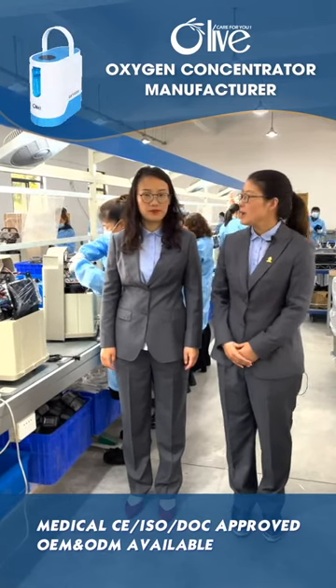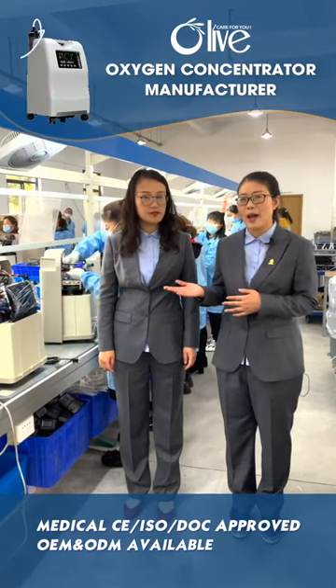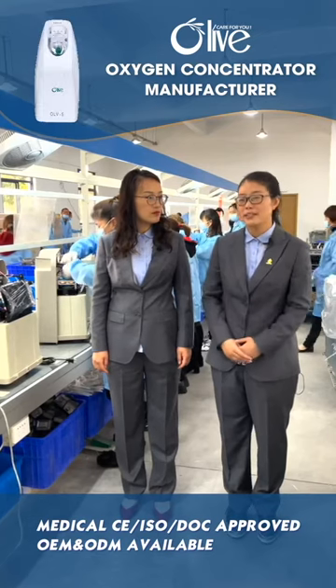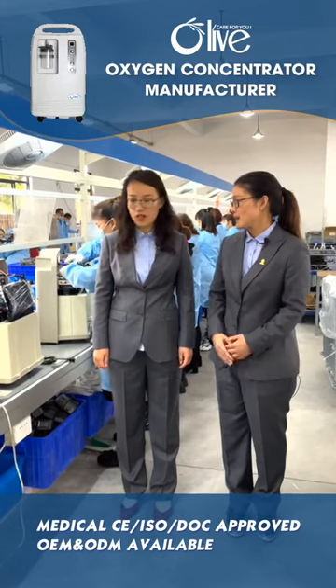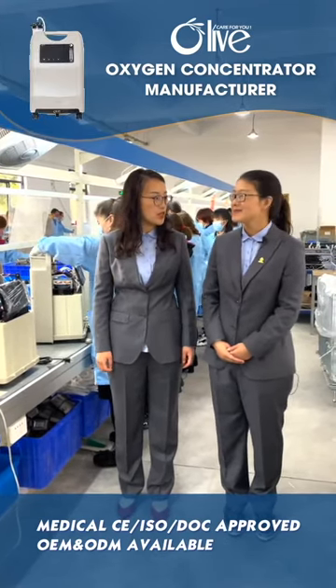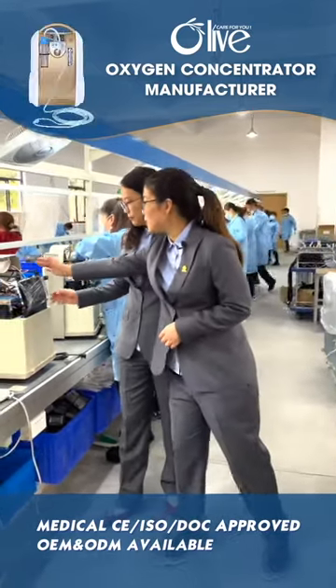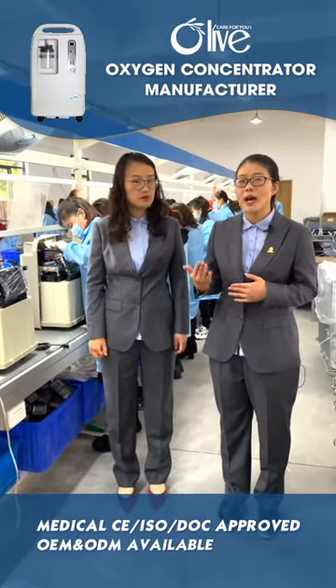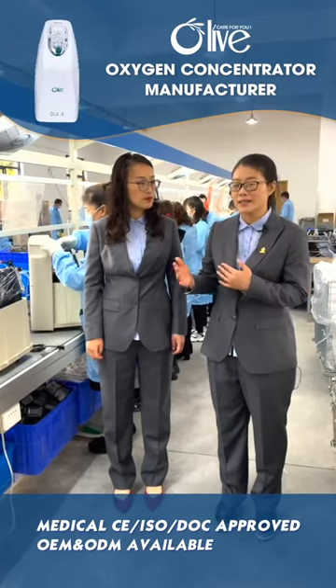Yes. All different countries have different plugs. For all the oxygen concentrators, we can provide different plugs to meet the requirements from different countries and different customers. So you can provide different plugs for different countries. Yes, that's no problem. And you see these cables, we will tie all the cables inside the oxygen concentrator, so it's cleaner inside.